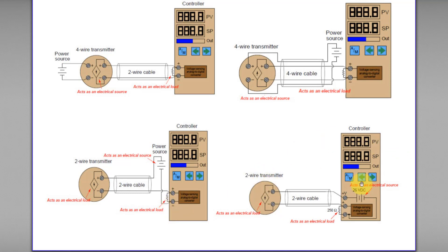Obviously, this transmitter and controller will both act as electrical loads. How about this one? If you observe carefully, the wire is actually connected to positive V — which is the positive voltage source. This is internally connected to the controller's internal power source. So this controller, in this case, acts as an electrical source to power up the whole loop. The power source will power the transmitter, so this transmitter acts as a load. And then we come to this positive and negative terminal here, and there is a load here. You may ask: how come there is a resistor here acting as a load? Is it okay to connect the wire from positive V to the transmitter, then back to the negative terminal? No.